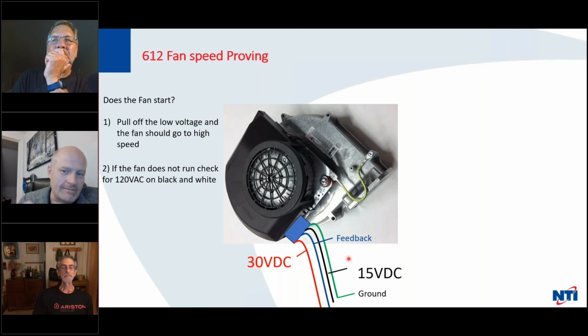So the control is like never your problem, or almost never. But at very least, measure the voltage to ground. You should, on any blower that's variable speed, find 2 wires, one will have a fixed voltage like this, 30 volts, and you're going to have one that really you can't get any reading on, and one that's a ground. And the one that we didn't talk about is the variable voltage. At very least, you should see that voltage change. So on this blower, you would measure between red and black.